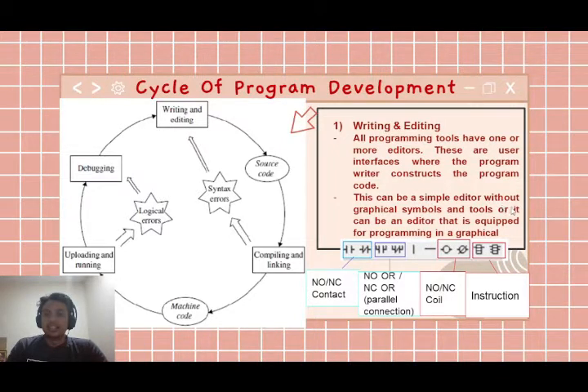This can be a simple editor without graphical symbols and tools, or it can be an editor equipped for programming in the graphical way. First, in this figure, we can see this is a normally open contact, then this is a normally closed contact. This is normally open or parallel connection. This is for normally closed or parallel connection. This is a normally open coil and this is a normally closed coil. These are instructions that we can do: keep instruction, set or reset instruction, or timer instruction.